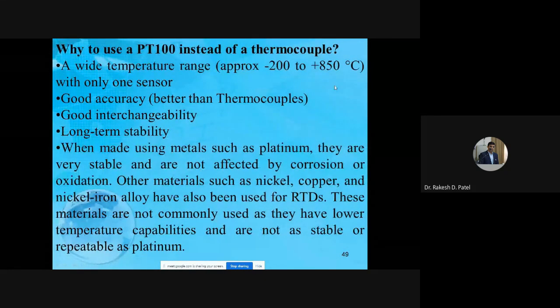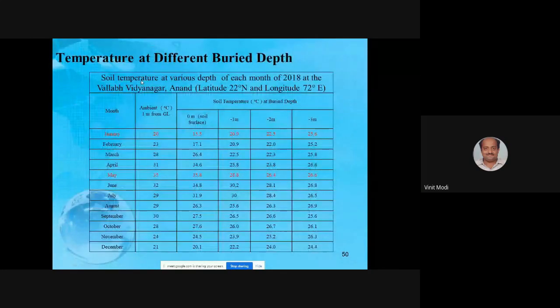Why am I using the PT100 instead of thermocouples? PT100 has a wide temperature range of approximately -200 to plus 850 degrees centigrade with one sensor, good accuracy, good interchangeability, and long-term stability. Metals such as platinum are very stable and are not affected by corrosion or oxidation. Other materials such as nickel, copper, and nickel iron alloy have also been used for RTDs, but are not commonly used as they have lower temperature capabilities and are not as stable for repeated use as platinum.